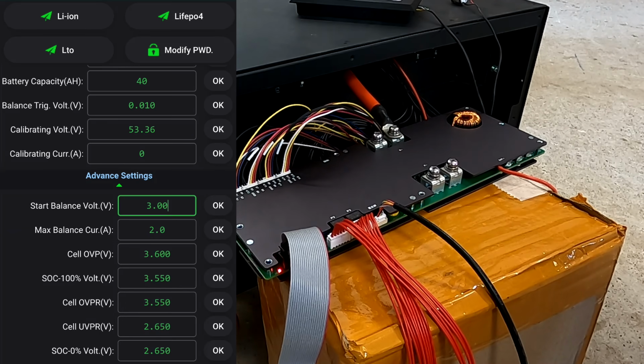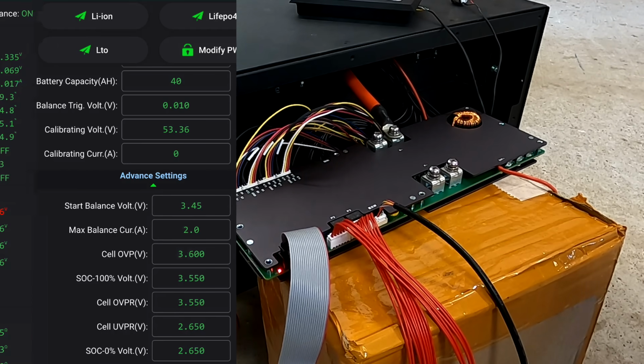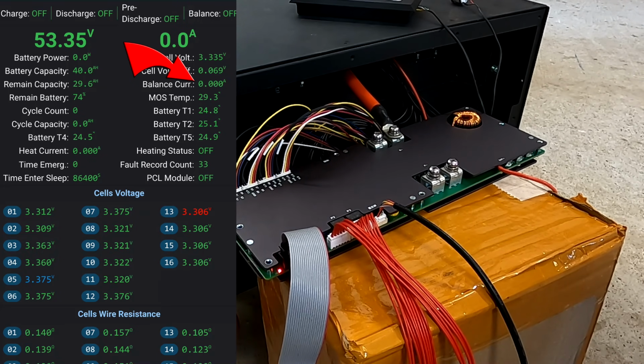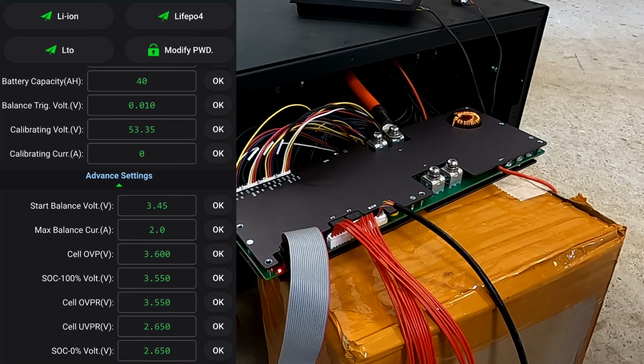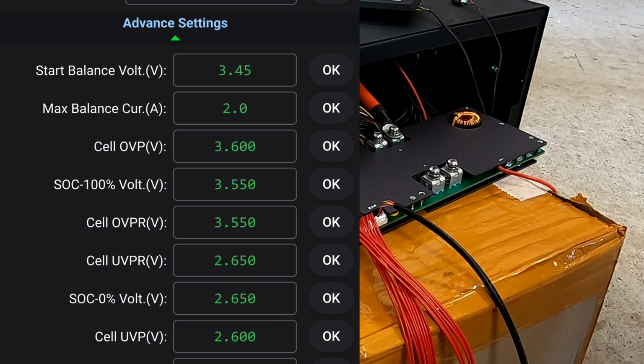So we change this one here to 3.45 volts and hit OK - you can always hear the confirmation beep of the BMS. This should make our balancer stop. Yes, now it has stopped because we have not reached 3.45 volts with one of the cells. Maximum balance current is 2 amps, and cell over-voltage protection is 3.6, which is fine.